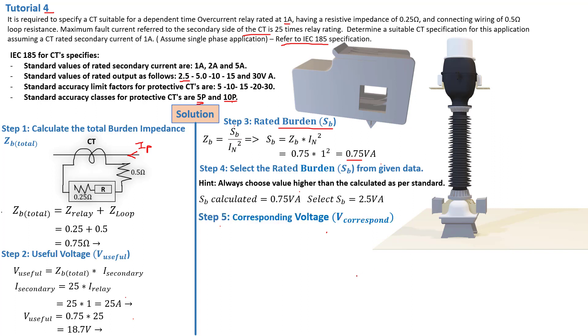Step number five: the corresponding voltage. The corresponding voltage is the voltage corresponding to the CT rated VA, given by SB divided by the secondary current I_N: 2.5 divided by 1 amp, giving us 2.5 volts.